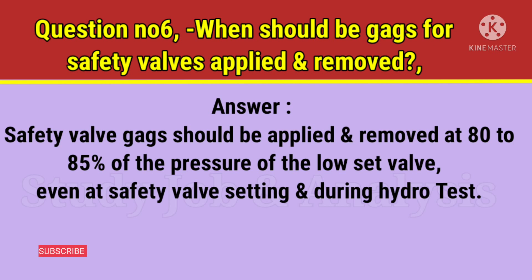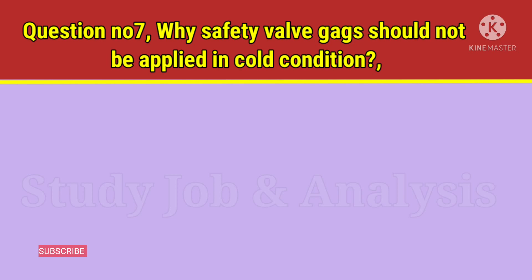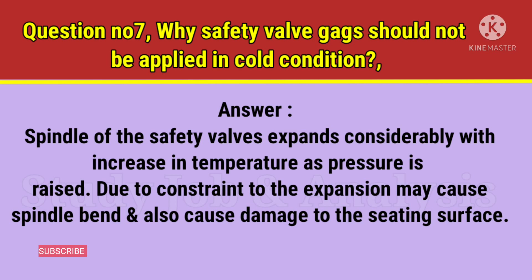Question number 7: Why should safety valve gags not be applied in cold condition? Answer: The spindle of the safety valve expands considerably with increase in temperature as pressure is raised. Due to constraint to the expansion, it may cause the spindle to bend and also cause damage to the seating surface.